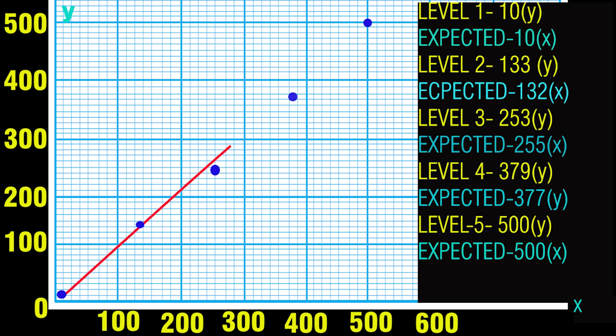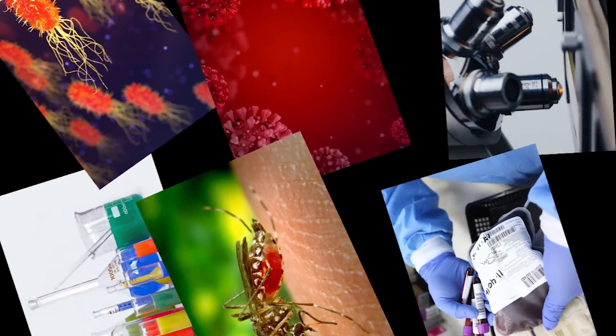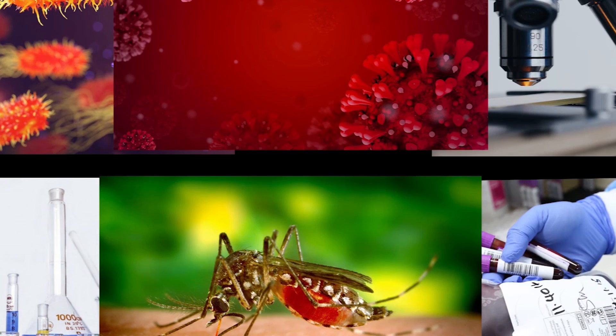The best-fit line may be drawn for experiments using equally spaced sample solutions. Visual assessment is a simple and intuitive tool for an expert technologist with good understanding of the method. Here I have explained a sample of glucose linearity and the graph. We will have another video on linearity errors to explain the common errors, common problems and issues, and how to solve those issues. Thank you, thanks for watching — please like, share, and subscribe.